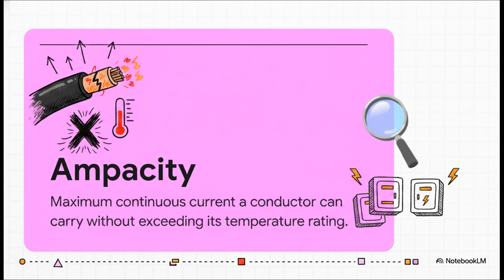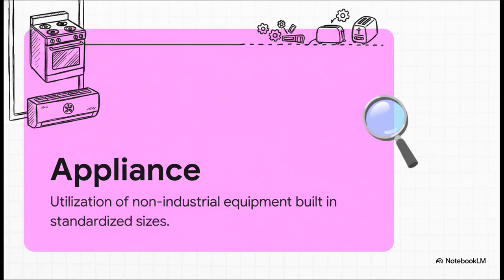All right, let's run through a quick sequence of these foundational definitions to see what's changed. We'll start right at the physical limits. Ampacity: this is the maximum current, measured in amperes, that a conductor can carry continuously, and the key here is doing that without getting so hot that it exceeds its temperature rating and melts the insulation.